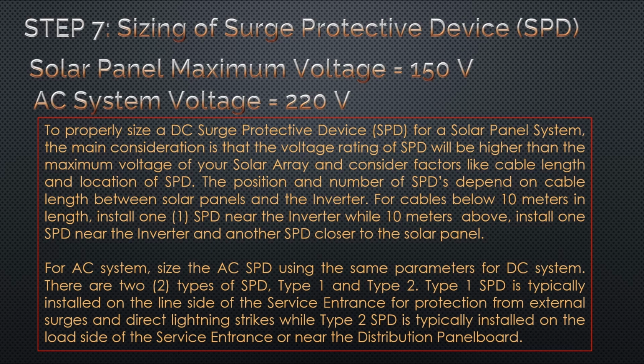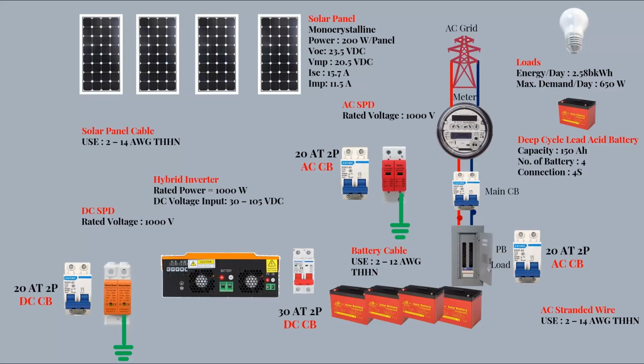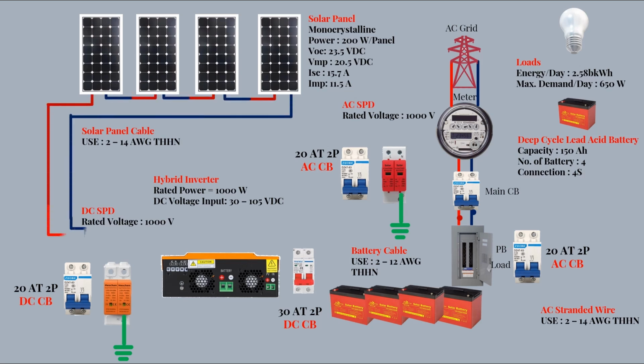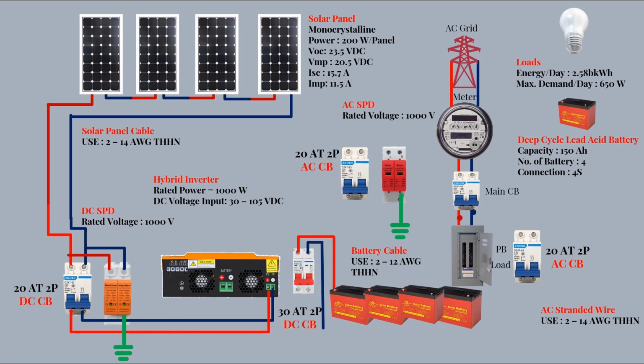For the AC system, size the AC SPD using the same parameters. There are two types of SPD, Type 1 and Type 2. Type 1 SPD is typically installed on the line side of the service entrance for protection from external surges and direct lightning strikes, while Type 2 SPD is typically installed on the load side of the service entrance or near the distribution panel board. Usually, the voltage rating of surge protective device for residential setup is 1000 volts. So this is the summary of the hybrid solar PV setup. In this diagram, it is also indicated all the values of parameters that are computed.